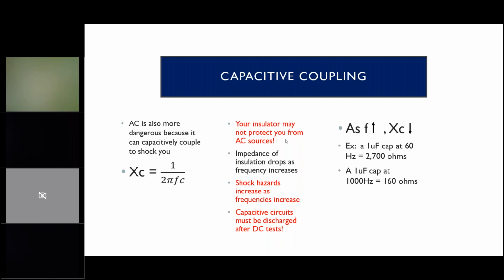So your insulator may not protect you from AC sources. Insulators are typically measured at DC, but at AC frequencies they can capacitively couple and still shock you. So as the impedance of insulation drops with frequency, shock hazards increase. Capacitive circuits must be discharged after a DC test.